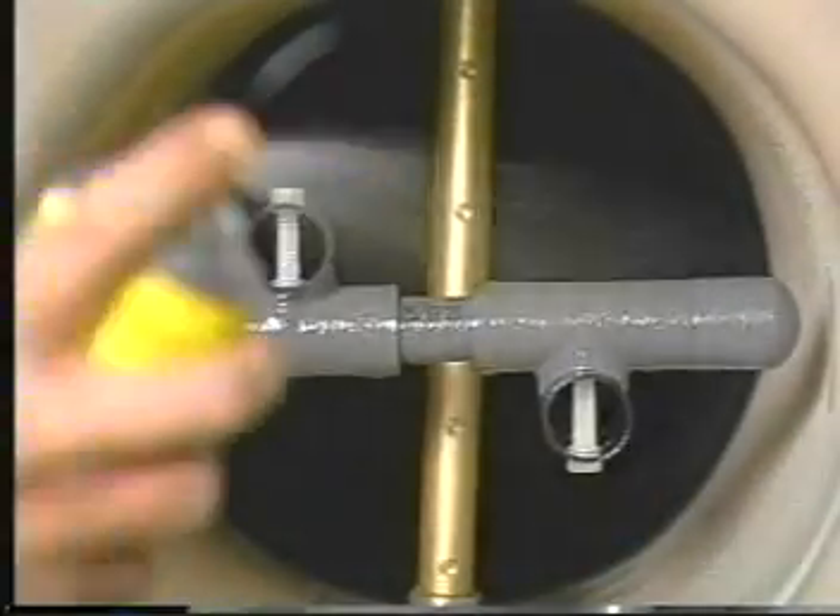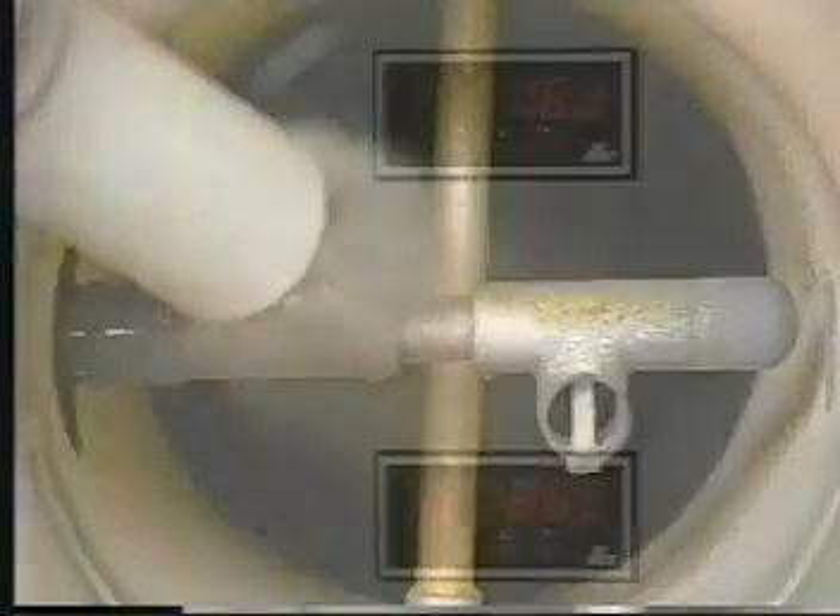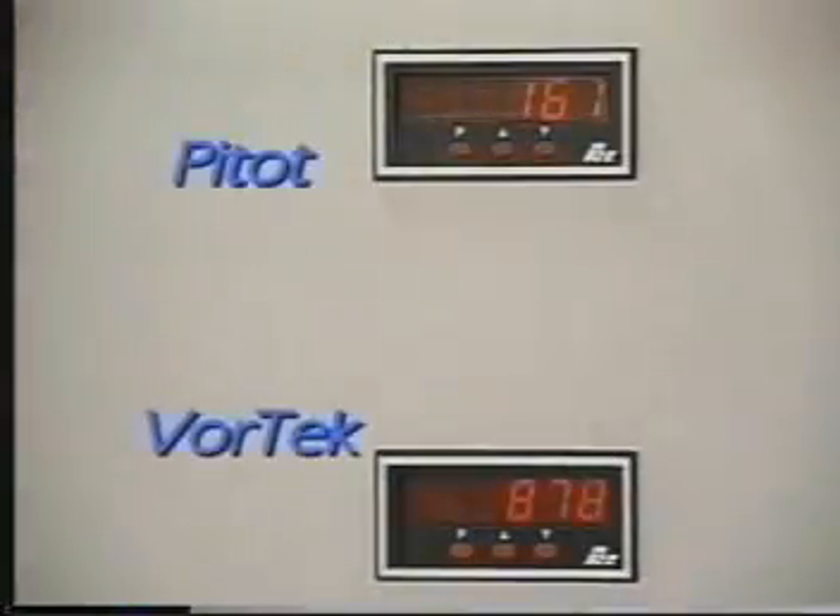To simulate contamination, both sensors were sprayed with an oil-based film followed by flour. In about a minute, the Pitot system reading is inordinately low, indicating that it has been plugged. The vortex probe, however, continues to function.